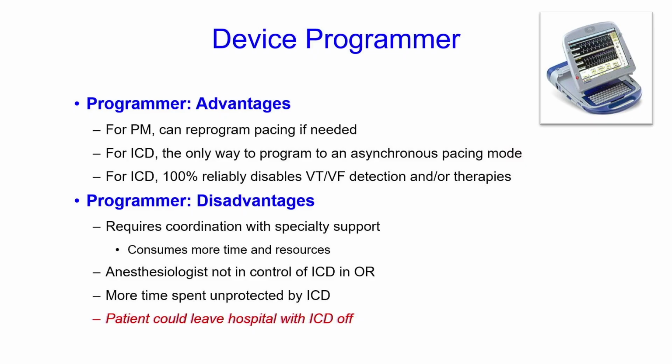The other way to reprogram the device, other than a magnet, is to use a programmer. The advantages of a programmer is that it can program the pacemaker however you want it to be programmed. For an ICD, it's the only way to program it to an asynchronous mode, so you would need a programmer to do that. And it 100% reliably disables the defibrillator so that you're not going to get inappropriate shocks.